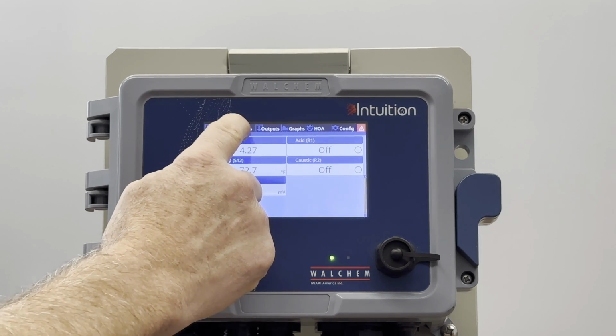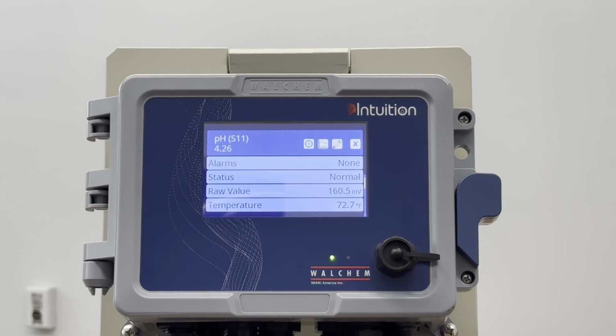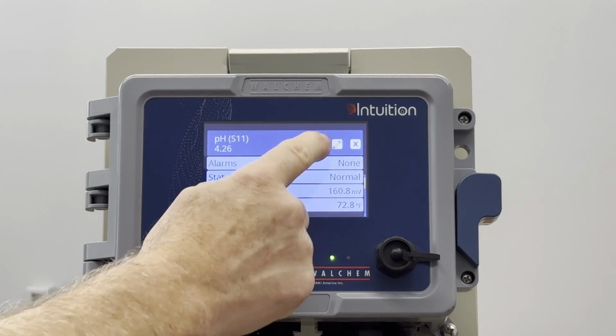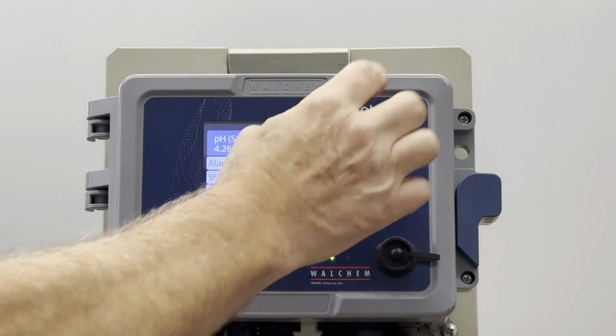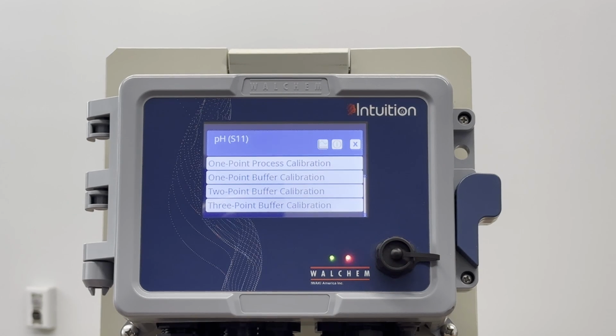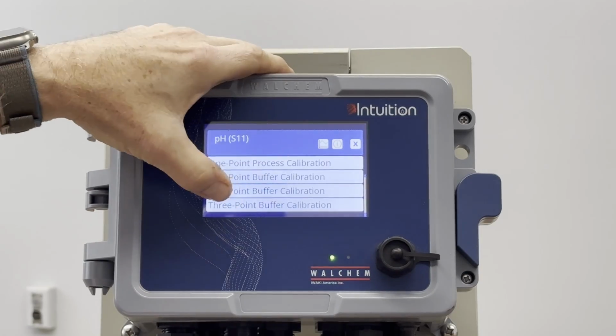If I go into either inputs or just select pH there, I can hit this little target button. I've got to push it a little bit harder. The target button takes me to all the calibration choices. You have a 1-point process calibration if you just want to adjust inline without doing any calibration. You could do a 1-point buffer calibration, a 2-point, or a 3-point. I suggest you always do the 3-point, especially if your pH can go anywhere from, say, 4 to 10. That gives us a good adjustment to go from 4 to 7 and then 7 to 10 in the control unit. So we're going to go ahead and do the 3-point buffer calibration.